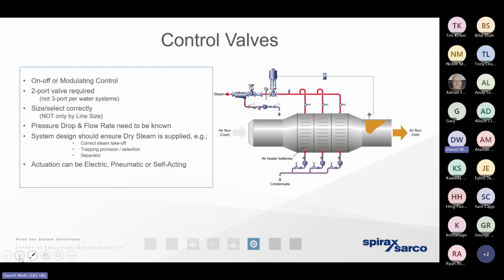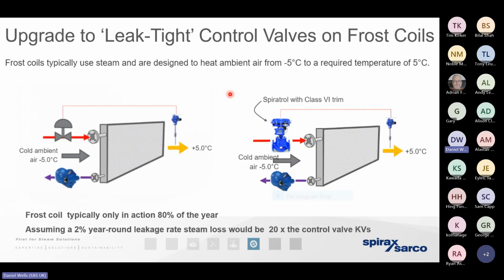So another rule of thumb for you here: when a control valve is correctly sized and correctly designed, we would expect that control valve to be sized approximately 2 pipe diameters smaller than the upstream connecting steam pipe. Better still if we've gone back to first principles and calculated the correct size of control valve. And also it tells us how and why those steam separators are critically important. So I want to give you an example here of how a control valve that's failing can create a problem.